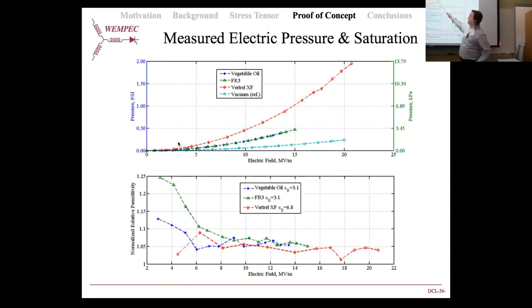So FR3 is a commercially available oil that's used by utilities. It's vegetable oil, but they put additives in it to keep it from going rancid. So if you're going to pour it into a transformer and have it sit on a pole for 30 years, they had to put a few things into it to keep it from going rancid. But that's actually something that's really cool, is that the utility industry is going to vegetable-based transformer oils in utility transformers and systems, which is pretty cool. They're ester oils. And then this is vegetable oil that literally came off the shelf from Hy-Vee.